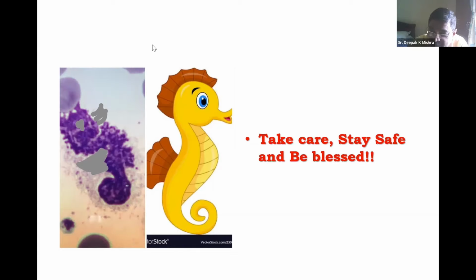And lastly, Parag Tavkar has come on the chat box, and he's saying it's possible to count up to 900 cells. The default setting of CellaVision is 200 white cells. So I asked him, why can't we make it 500? Because when you have a very low number of blasts in the peripheral blood post-induction or post-consolidation, you have to examine a large number of WBCs to find one or two occasional blasts.